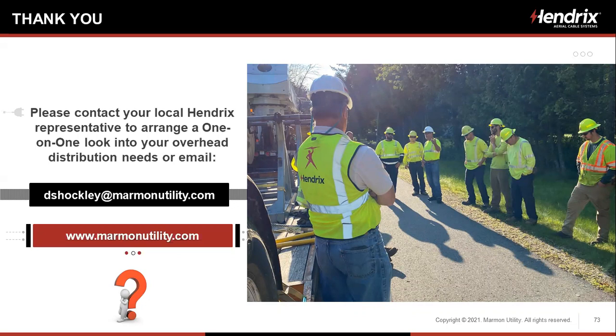Yes, Kristen, great question. Yeah, we do this all the time. We build lines through national forests, whether it's 25 or 35, 46 or 69 kV. And you've got a 2, 3, 4, 5 mile line. You don't want to pay the premium for high voltage covered conductor. Yes, we'll do 2, 3, 4, 5 spans here of spacer cable. Then we'll do maybe half a mile of bare wire, then a quarter mile of spacer cable, and half a mile of bare wire. Yes, you can go back and forth between bare wire and spacer cable. I guess the only caveat is that you have to buy a couple of arresters, because every time you do a transition between bare wire and covered conductor, you have to install arresters to protect that covered conductor.